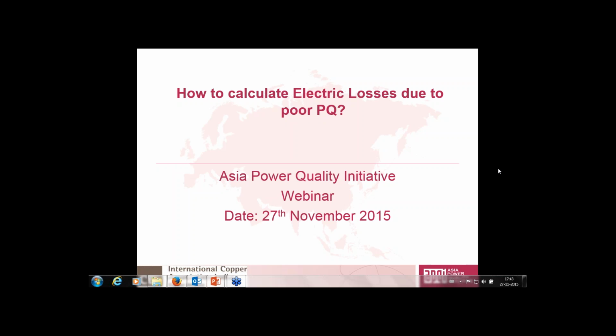Okay. Now the next question comes to Frank. If a motor is running with VFD and at 40% loading, what is the effect on harmonics level? Could you just repeat the question again, please? If a motor is running with variable frequency drive, and at 40% loading, then what will be the effect on harmonics level?